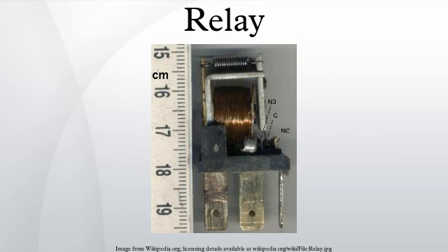In the particular case of high inductance circuits such as motors, other issues must be addressed. When an inductance is connected to a power source, an input surge current or electric motor starting current larger than the steady current exists. When the circuit is broken, the current cannot change instantaneously, which creates a potentially damaging spark across the separating contacts.